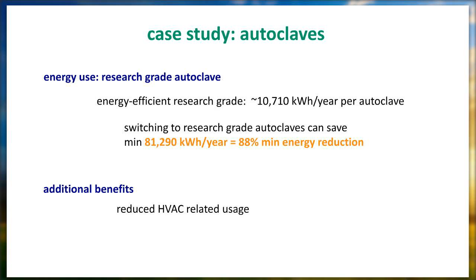One of the other really cool benefits of switching from a medical grade to a research grade is that medical grade autoclaves tend to have their own rooms. It's not uncommon for those rooms to have 20 air changes per hour, because it's assumed that these are running all the time. They get very, very warm, and they are often used to sterilize things that might have an odor to them. By switching to something a bit smaller and more compact, that we know isn't being run all the time, we can dial back the number of air changes per hour. Research-grade autoclaves are really only run about 5 times a day at most.